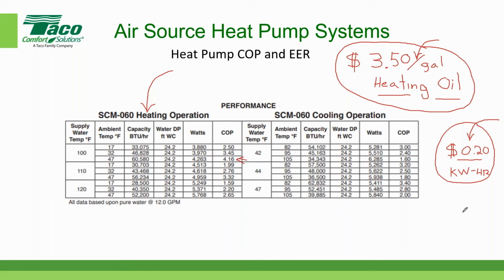Does the COP take into account the actual energy to run the unit itself? Yes, it does. Remember, the formula is based on the energy input, which is a part of the COP calculation. And the 42-degree supply water on the cooling side comes from the system, correct? Yes, if you're designing your cooling system, its capacity is based on an entering water temperature of 42. If you notice, the manufacturer gives you a range here from 42 to 47. You could design an HVAC system that has an entering water temperature of 47 degrees. Most of the time, it's around 44 degrees. 47 would be a bit borderline in some areas that have to do a significant amount of dehumidification. But you could still do it. It just becomes expensive in terms of surface area.